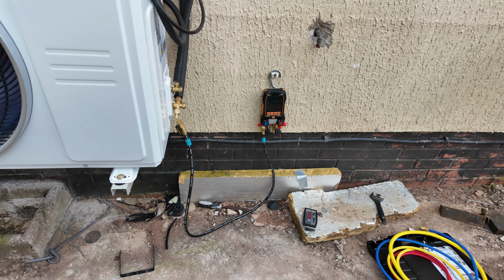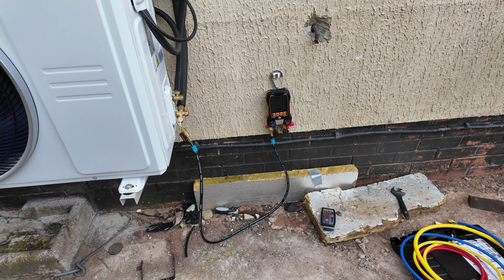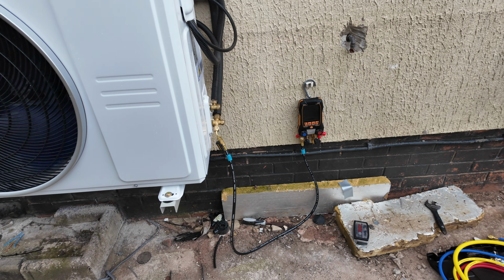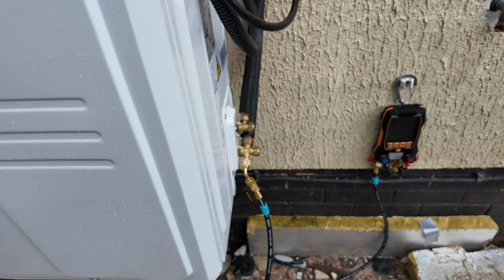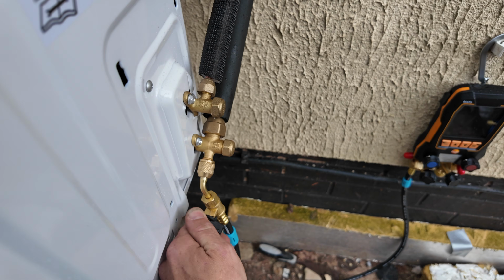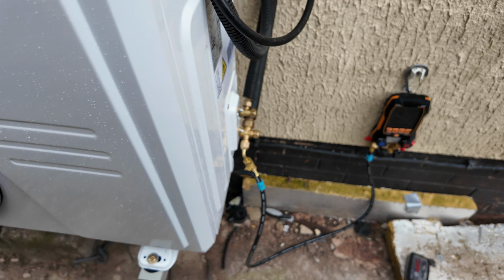Yeah, there you go, so yeah, just got it on cooling now. We can disconnect the gauges outside once that's in cooling mode. Oh, it's just in cooling now. Just turned it off, so it should be sucking through the line there, should be sucking all that out. So turn that one off, and we can disconnect that one with your gloves on. Then we can get some gloves.